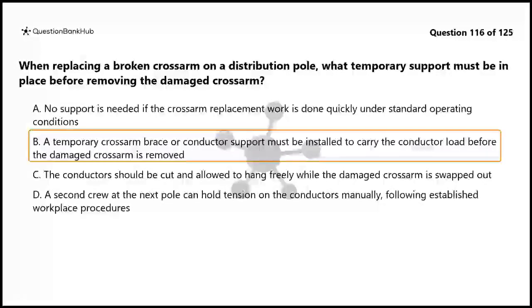The correct answer is B. Before removing a damaged crossarm, a temporary crossarm brace or conductor support must be installed to carry the weight and tension of the conductors. Removing the crossarm without temporary support allows the conductors to fall, creating contact hazards and potentially snapping under uncontrolled loading. Working quickly is not a substitute for proper rigging. Cutting conductors creates an outage and additional repair work. Manual tension holding is unsafe and impractical.